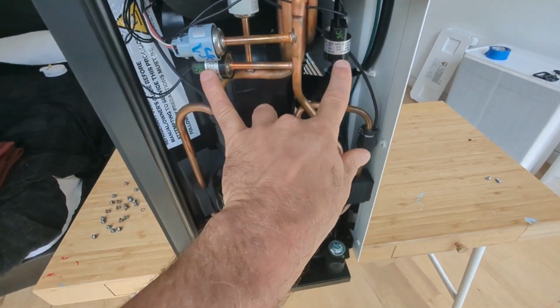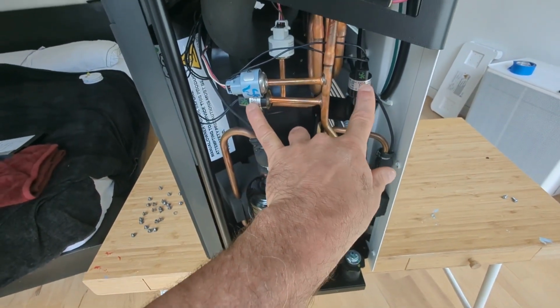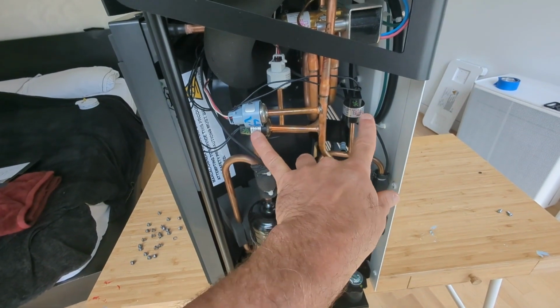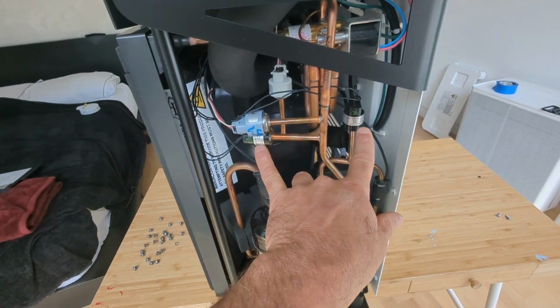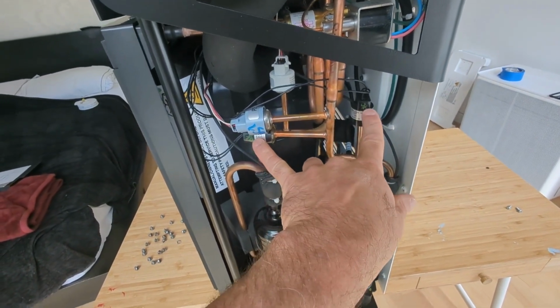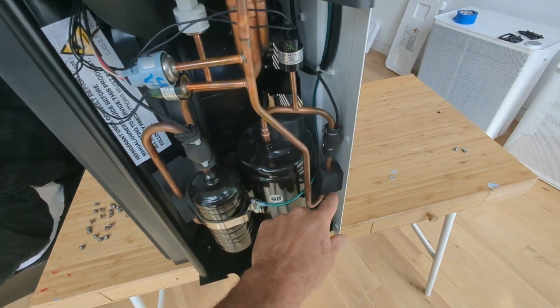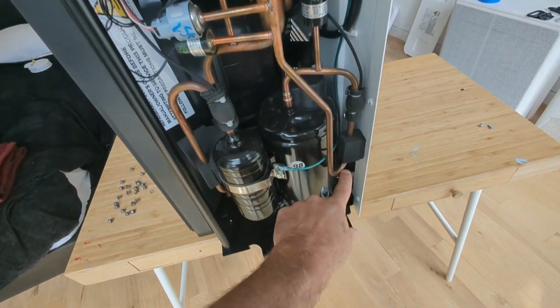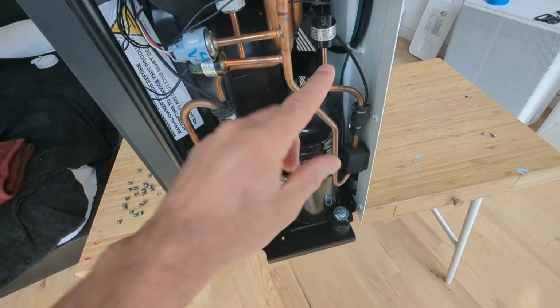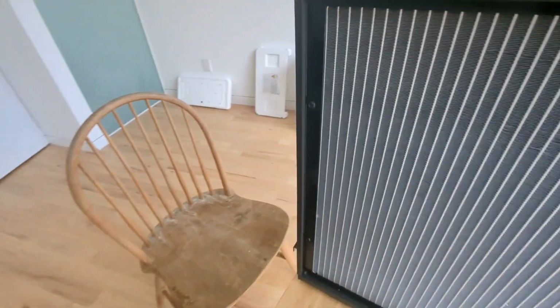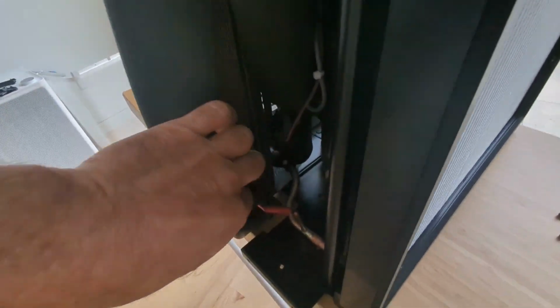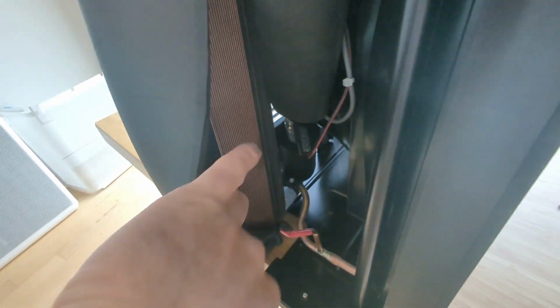And so here are those 2 pressure sensors. I don't know why they used 2. It might just be a safety thing where if one of them fails, they want the other one to trigger. But really, you would expect the pressure that these 2 guys are seeing would be the same since they're connected by this tube. The freeze lockout is buried in here next to the heat exchanger, which is this block here. And it's hopefully set to trip before you get down to the freezing temperature of that glycol.